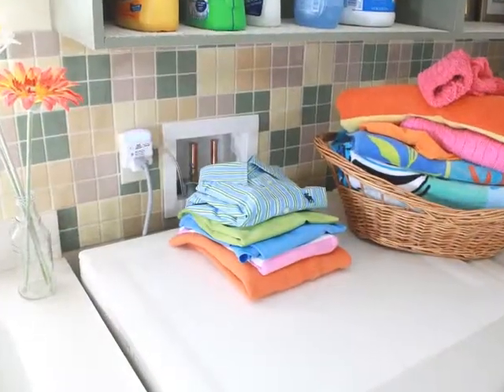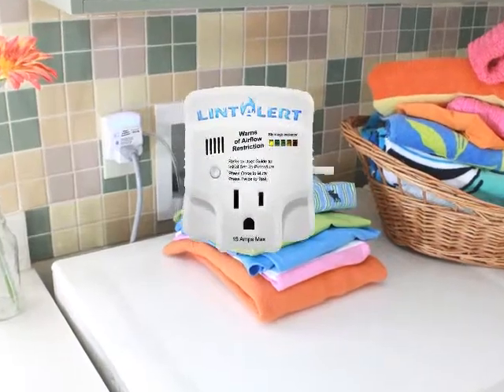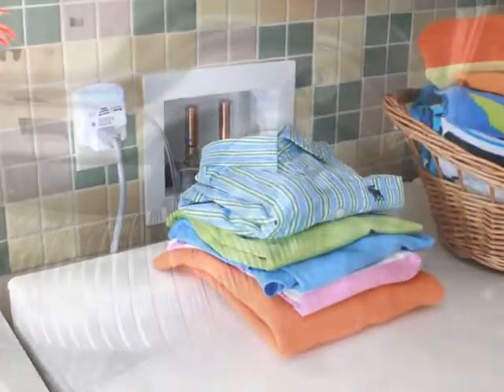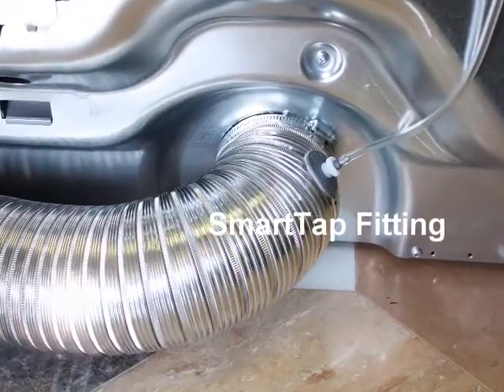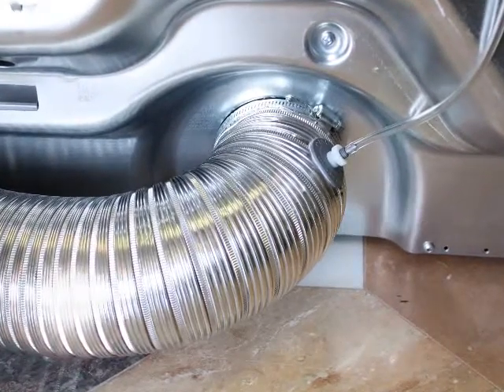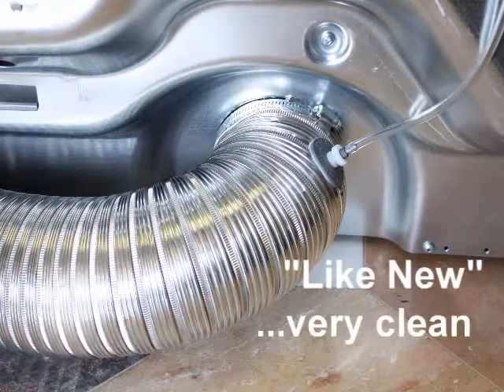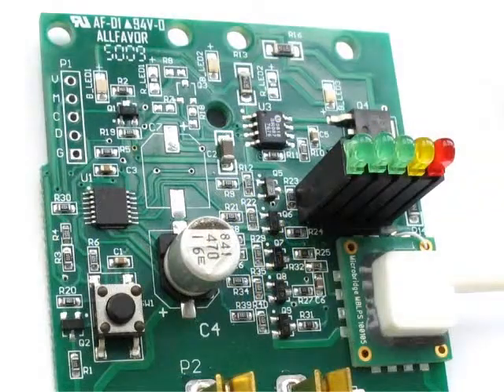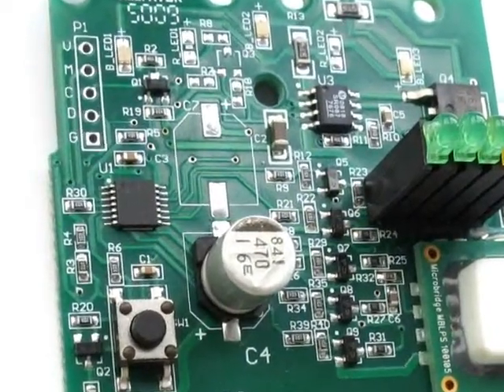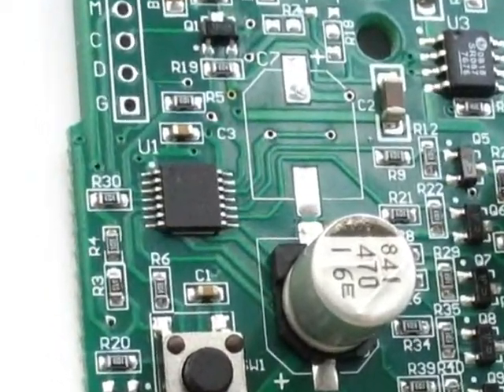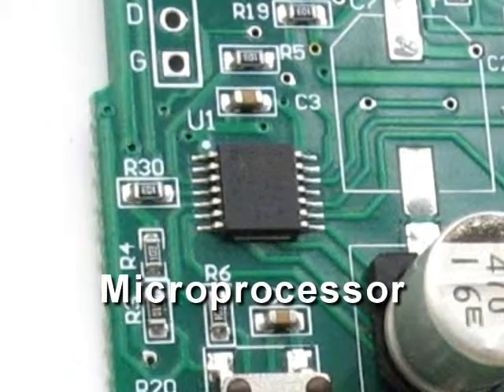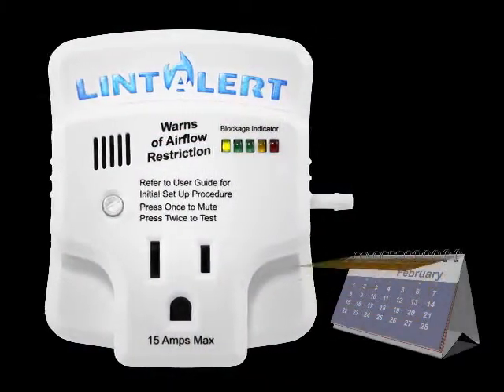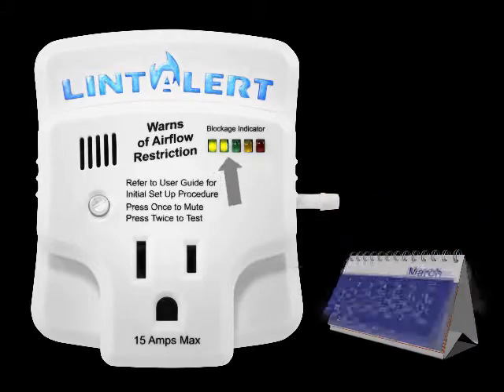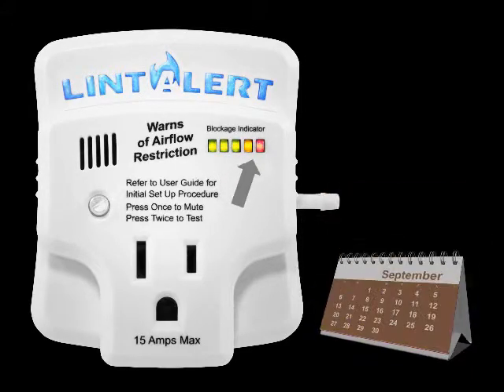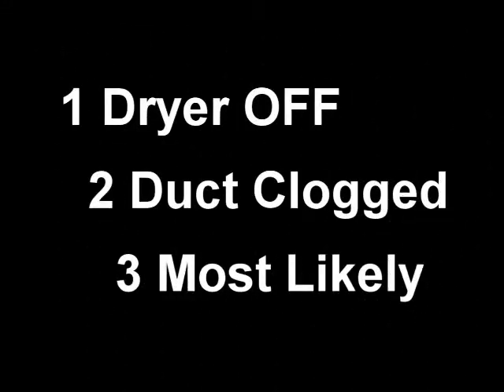In order for the LintAlert to accurately monitor the air pressure levels in the specific dryer's exhaust duct, the device needs to be calibrated to your particular system at a like-new or very clean state. In technical terms, a clean value must be recorded to memory in order to determine the proper interval proportions. These intervals are then progressively illuminated over time through the LED light bar. Let's start with demonstrating 3 different calibration attempts of the LintAlert.